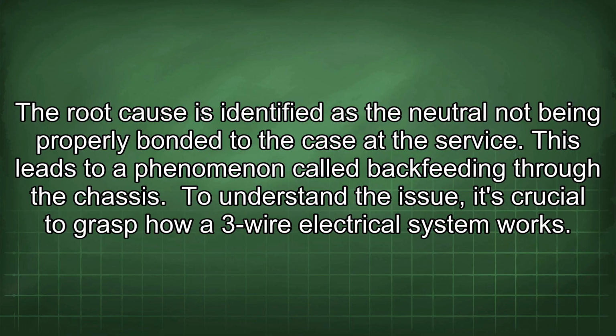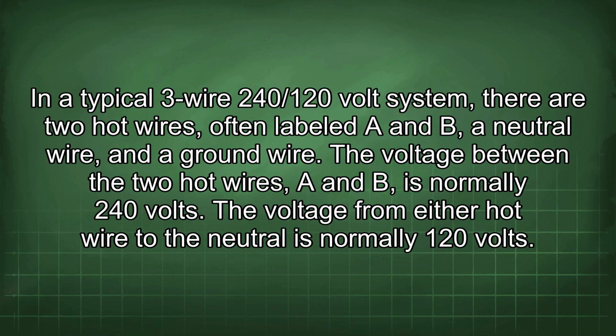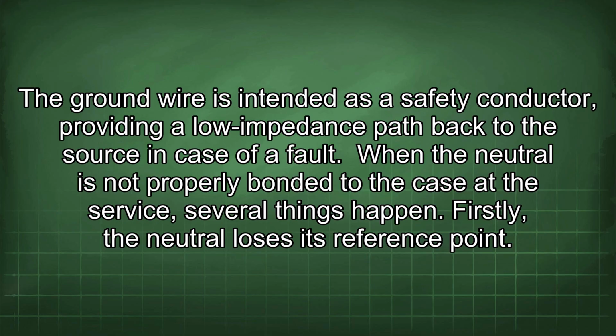To understand the issue, it's crucial to grasp how a 3-wire electrical system works. In a typical 3-wire 240/120 volt system, there are 2 hot wires, often labeled A and B, a neutral wire, and a ground wire. The voltage between the 2 hot wires A and B is normally 240 volts. The voltage from either hot wire to the neutral is normally 120 volts. The ground wire is intended as a safety conductor, providing a low impedance path back to the source in case of a fault.